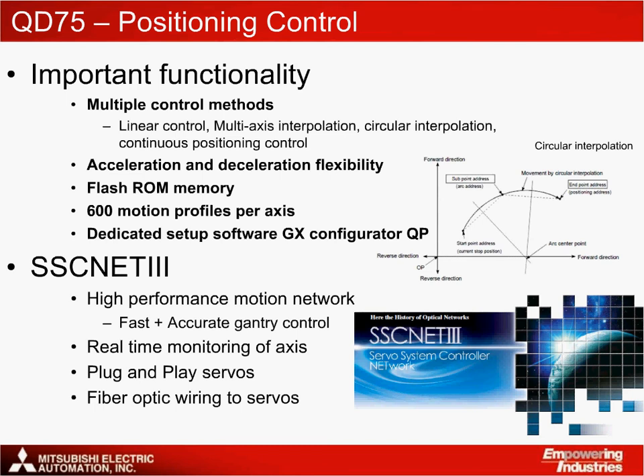The QD75 is the motion controller for synchronising movements between the X, Y and Z axes. The QD75 stores the parameter data for both servos and positioning operations and reacts to the requests sent from the PLC CPU. There are one, two and four axis modules available for the QD75. As this example outlines a three-axis system, the QD75 MH4 has been selected. Key functions for this module are: linear control for point-to-point addressing along one axis; multi-axis interpolation for point-to-point addressing along multiple axes; circular interpolation for faster movement between points where lifting of the workpiece is required; continuous positioning control for when the workpiece has to be moved to multiple points in one positioning operation; and acceleration and deceleration functionality of the workpiece.